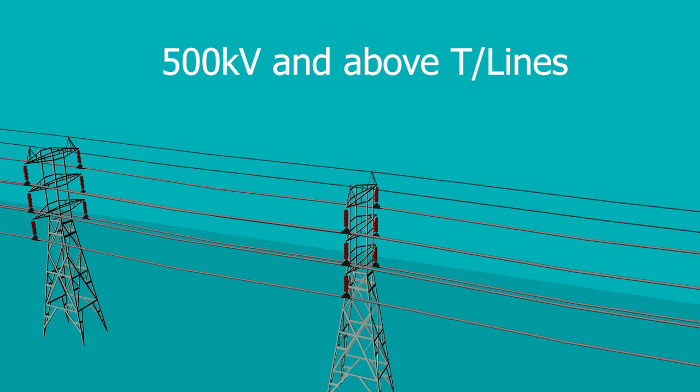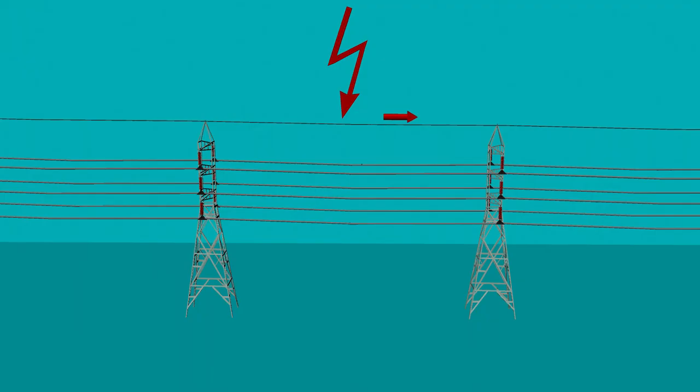Normally up to 220kV transmission line voltage levels there is a single earth wire used, while on 500kV and above voltage levels there are normally two earth wires installed on the towers.